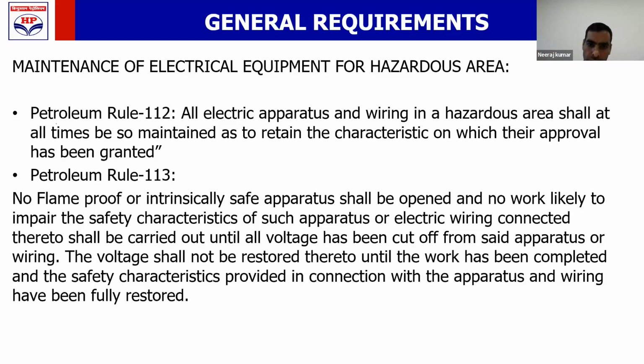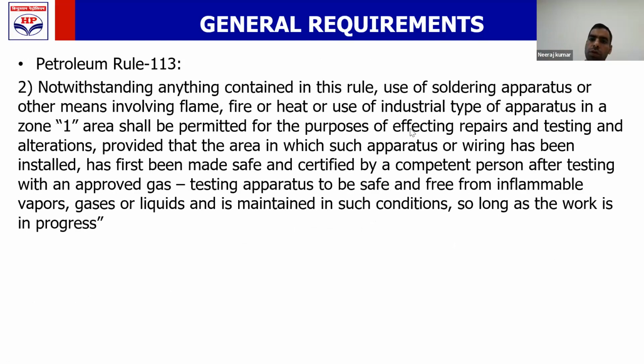Even though you are not doing any maintenance on these equipment, still, to ensure that their flame-proof property or their explosion protection properties are maintained, you have to ensure that they are maintained in such a way for which their certificate was given. Primarily, it will require tightening of nut bolts, using suitable type glands, or, if your gland and your equipment's threading are not matching, using an extension. That extension should also be certified as the certification of your equipment. If you follow the requirements, then this will meet the requirement of this standard.